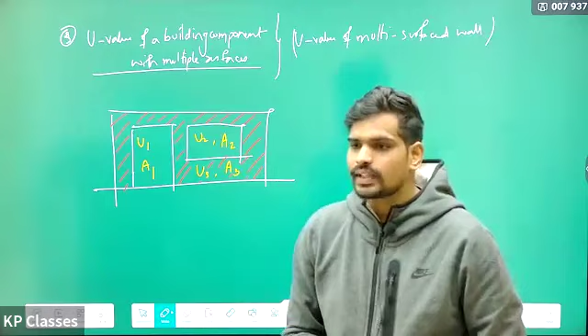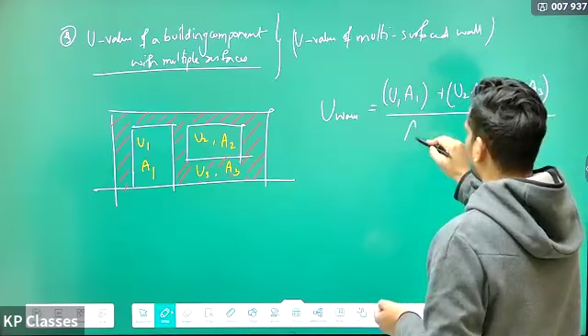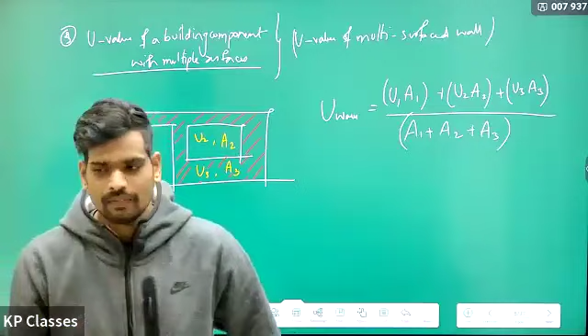Right? So for every surface, you'll need to know the U and the area of that particular material or that particular section. If you know that, you can find out the overall U value of the wall as U1 into A1 plus U2 into A2 plus U3 into A3, divided by total area, that is A1 plus A2 plus A3. This will give you the U value of the wall. Now again, I'm not deriving it, I'm just revising the concept over here. The derivation, however, is simple, but I'll not go into those details. If we keep on deriving each and every formula, we'll not be able to revise everything in these 3 hours. So our focus is on revising things here. Right? So U value is U1A1 plus U2A2 plus U3A3 upon A1 plus A2 plus A3.